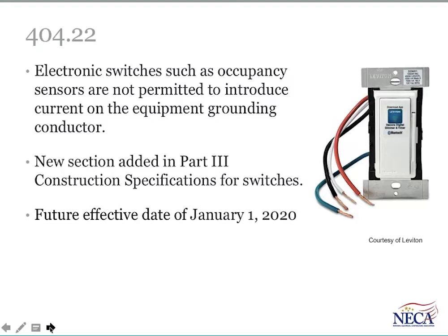It's not as problematic when you introduce milliamps of current through one device on a system, but if a building has a few thousand of those devices, milliamps can turn into amperes real quick, and you really shouldn't have that level of current on equipment grounding conductors. There's a future effective date tied to this to give the manufacturers time to deal with those types of devices under the current product standards that are in the pipeline.